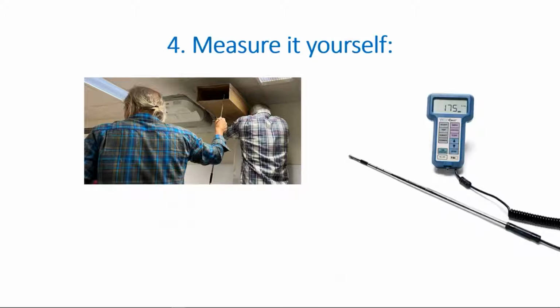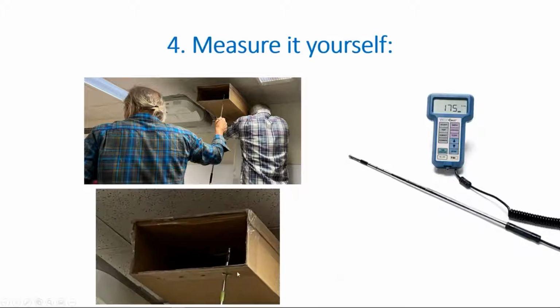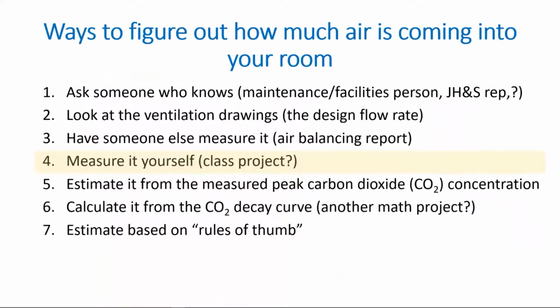We took a cardboard box and put it over the diffuser, and you can see Murray here putting the probe up into there. And we have 4 holes on the bottom, and we put tape on the probe so we know exactly where to place this, and then we take the average over the thing. But you probably don't have one of these machines, so what are you going to do?